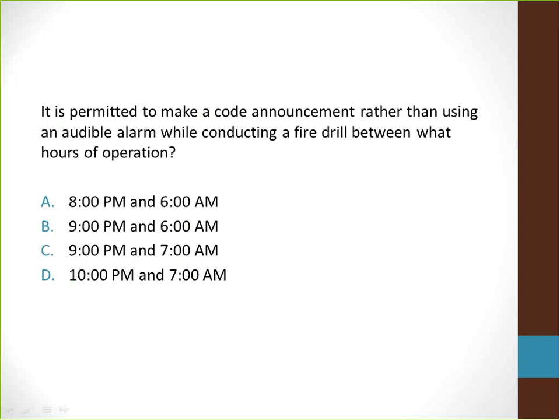It is permitted to make a code announcement rather than using an audible alarm while conducting a fire drill between what hours of operation? A, 8pm and 6am; B, 9pm and 6am; C, 9pm and 7am; D, 10pm and 7am. Answer B is the correct answer here because according to NFPA 101, this is permitted.